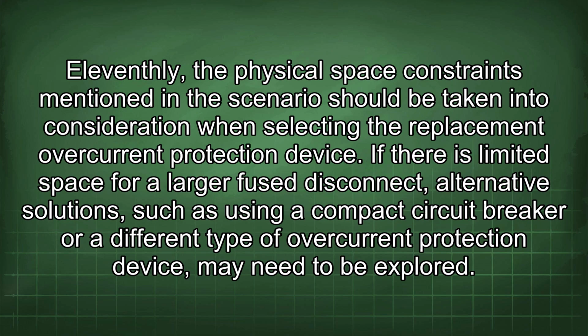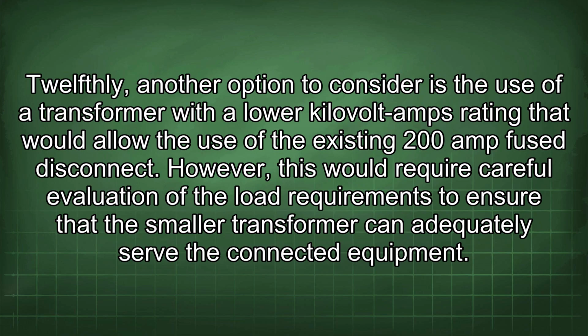11thly, the physical space constraints mentioned in the scenario should be taken into consideration when selecting the replacement overcurrent protection device. If there is limited space for a larger fuse disconnect, alternative solutions such as using a compact circuit breaker or a different type of overcurrent protection device may need to be explored. 12thly, another option to consider is the use of a transformer with a lower kilovolt amps rating that would allow the use of the existing 200 amp fuse disconnect.